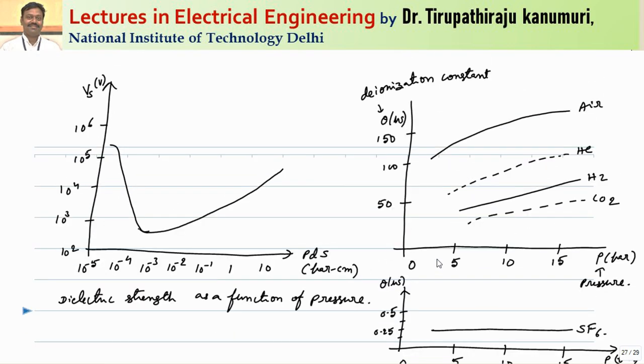Let us see how, with a change in the pressure of the gas between the contacts, the dielectric strength changes. It is observed practically that if you increase the pressure from 10⁻⁵ up to nearly 10⁻³ bar·cm, the dielectric strength goes on decreasing — it has an inverse characteristic. But after that, if you increase the pressure further, it has a positive characteristic: as the air pressure is increased, the dielectric strength is increased. So if you maintain the pressure above 10⁻³, the dielectric strength will go on increasing.